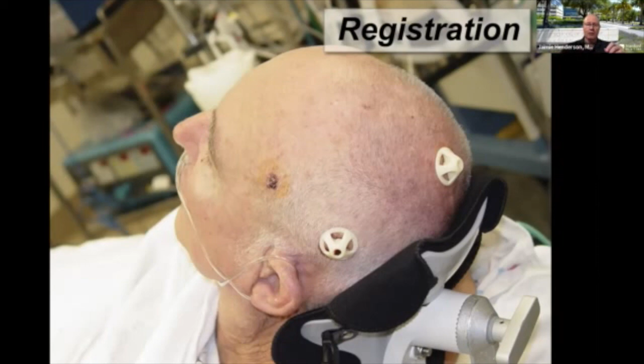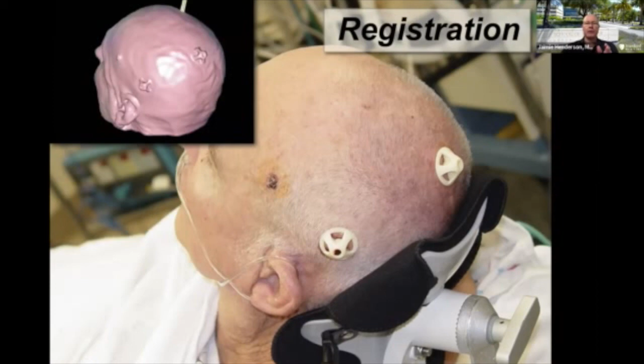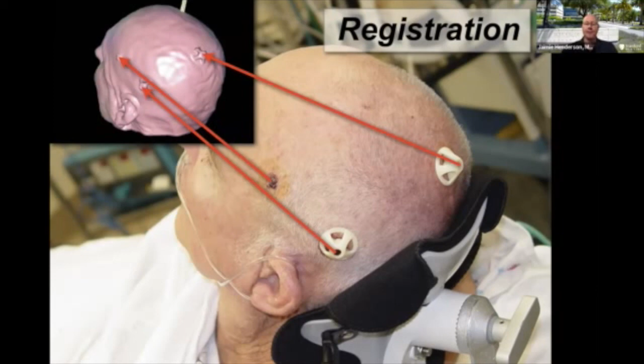So here are those same markers on the reconstructed CT scan. We now say, okay, how do we match those markers to the CT scan? The reason for this is because I've done all of our planning on the CT scan, so we now have to translate that planning into real life. This is the step that makes that happen. And we do this by touching each one of these markers with an instrument. You can see I'm holding that instrument that has reflective spheres on it. There are infrared cameras, each of which has an infrared emitter around it, and the infrared light leaves the camera, bounces off those spheres, and comes back to the camera. Each one of those spheres looks like a circle. And by calculating the center of that circle, and by knowing the geometry of the instruments, we can tell exactly where that instrument is in three-dimensional space to a very small accuracy, about 1/4 of a millimeter.